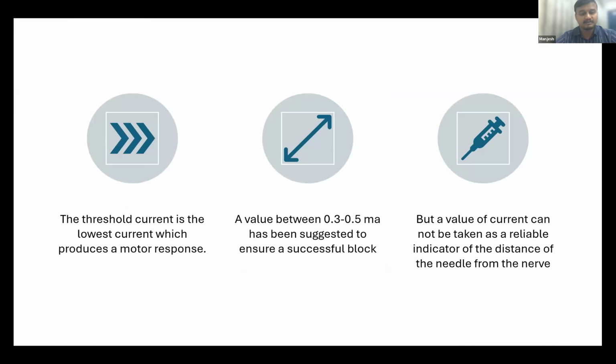Coming to the threshold current, it is the lowest current which produces a motor response, and a value between 0.3 to 0.5 milliamperes has been suggested to ensure a successful block in regional anesthesia using a peripheral nerve stimulator. But a value of current cannot be taken as a reliable indicator of the distance of the needle from the nerve, because it depends on the needles that we use as well.